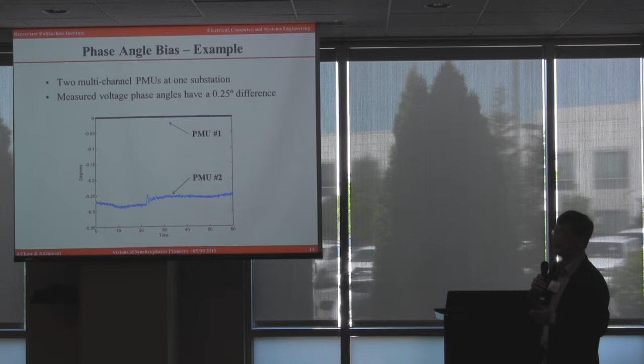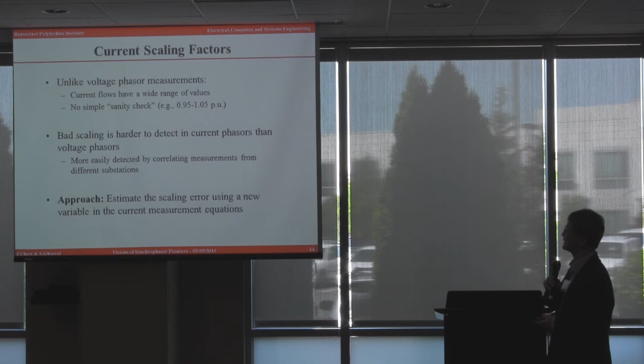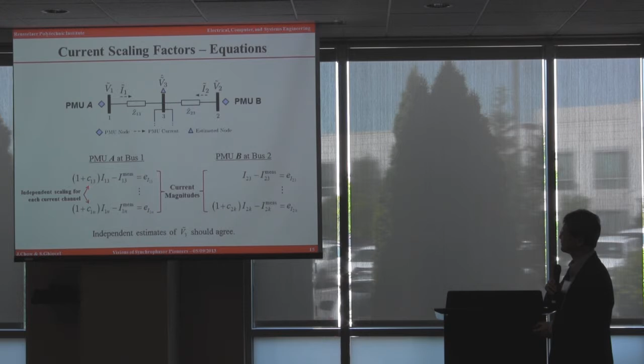The other thing we found is the issue with CTs and PTs. Now, voltage is a lot easier to analyze because you know that it's between 1.0 per unit plus or minus a few percent. Current can vary during the day, so it's very difficult to catch issues in current. Whenever we have a large current scaling error, we actually can correct for it. And the idea is very simple, putting in some scaling factors over here.